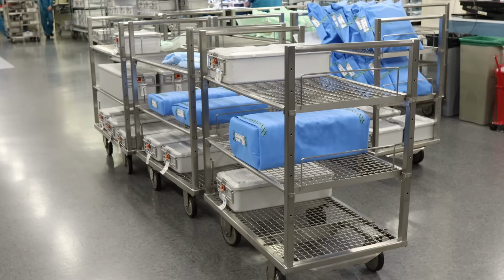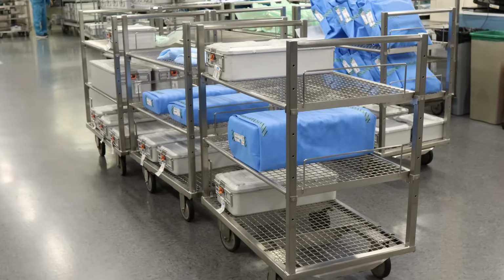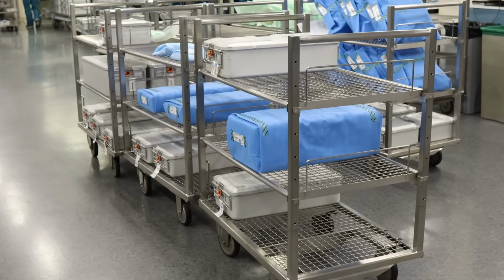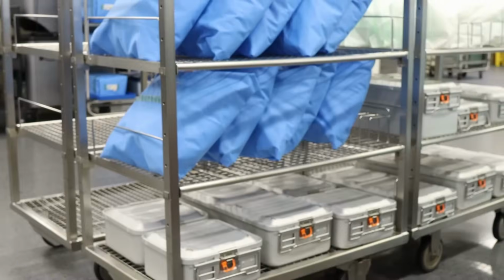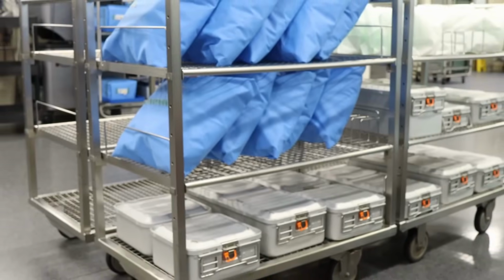Sterilization has many other factors to consider, such as load weight, what is the density of all the instruments that are able to be sterilized in a single cycle. Type of items being sterilized like metal, plastics, cannulated items, which all factor into the parameters and types of sterilization to be used. Some items have proven to take longer to sterilize than others and will have longer cycles. And lastly, load configuration, how the different types of packages are arranged on the sterilizer racks, considering spacing and cooling time. Metal trays and wrap trays tend to cool at different rates and could cause condensation, making trays unsterile once they are out of the sterilizer.